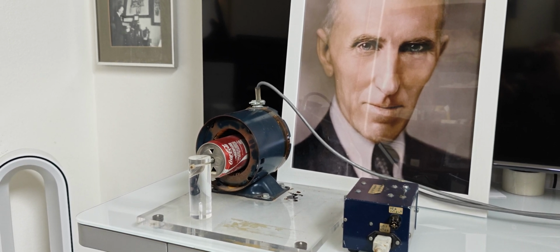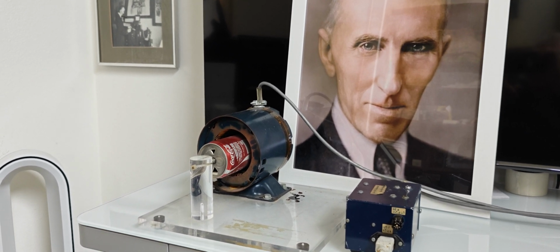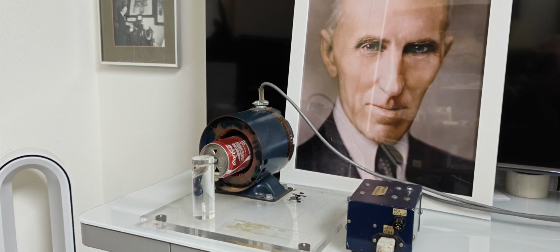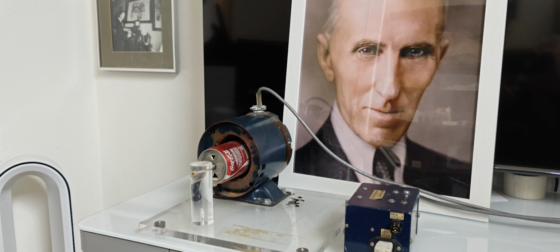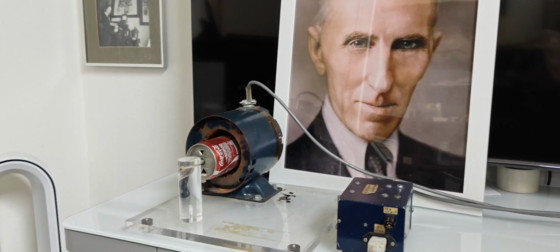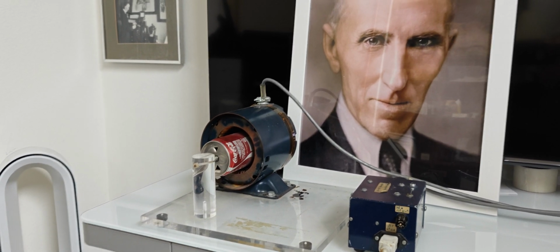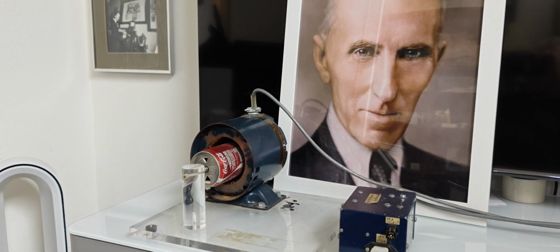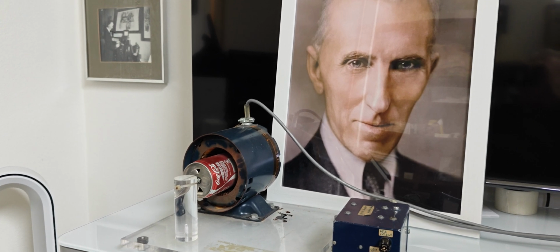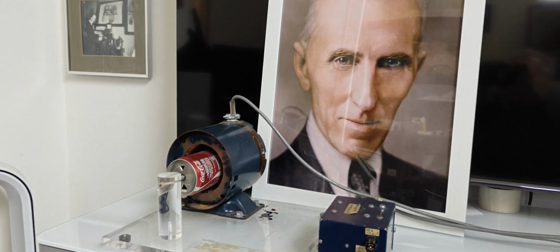You also saw that this one does have a very good starting torque, because you can just turn it on and it starts with full force from the very beginning until it approaches close to the synchronous speed for 60 hertz operation. That is 3,600 revolutions per minute, but typically the actual running speed of this squirrel cage rotor would be 3,550 or so.